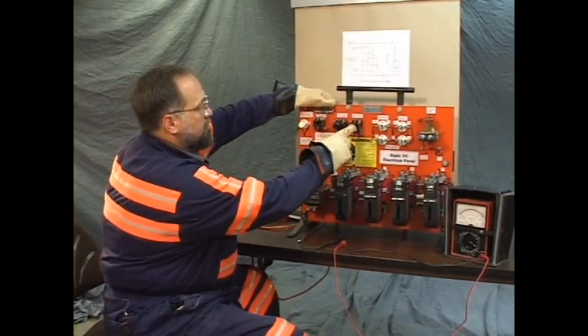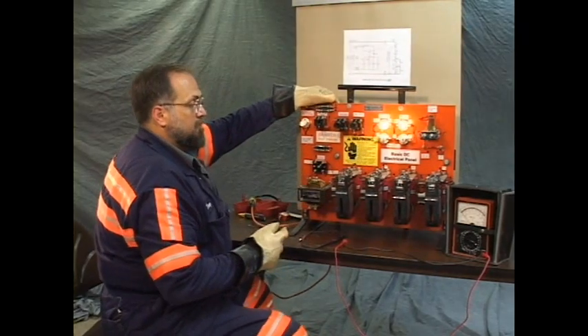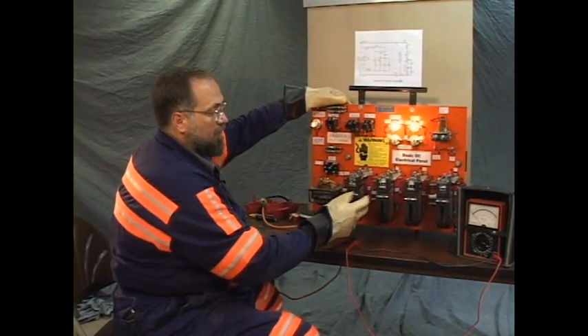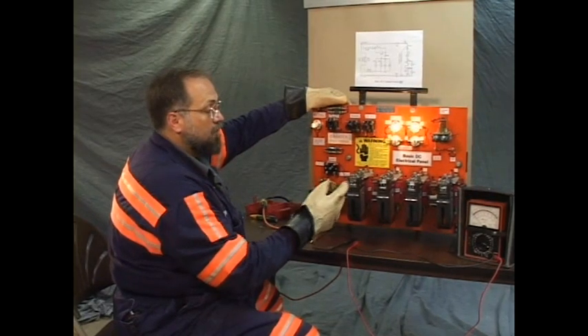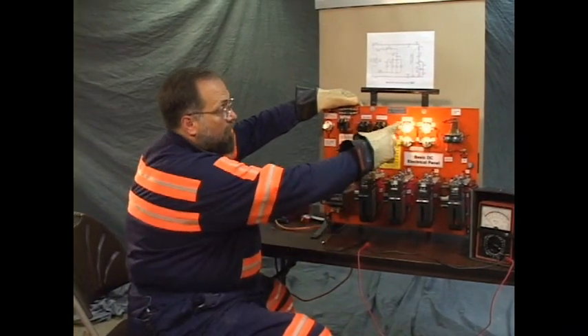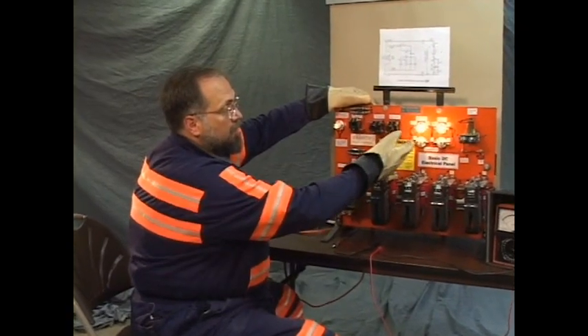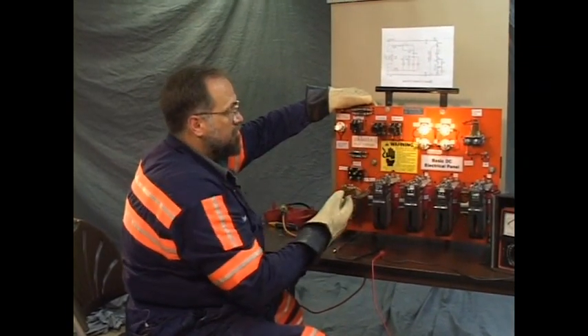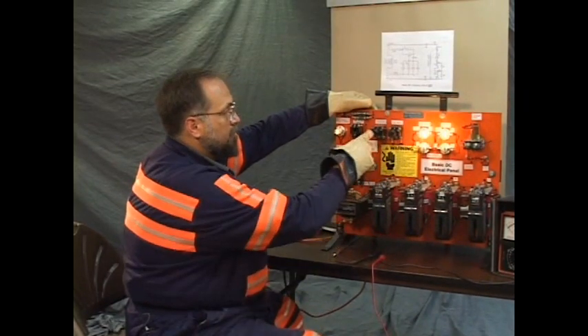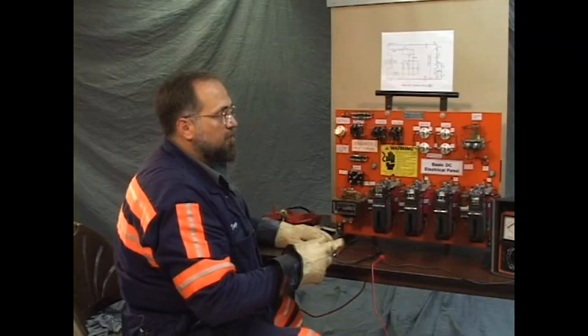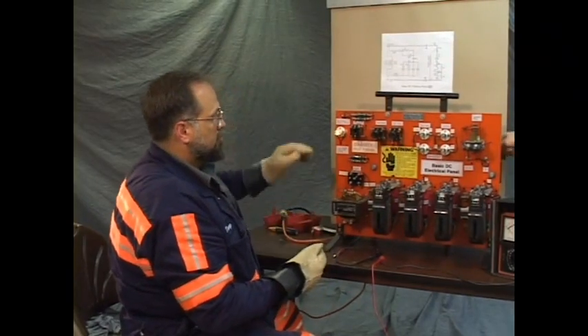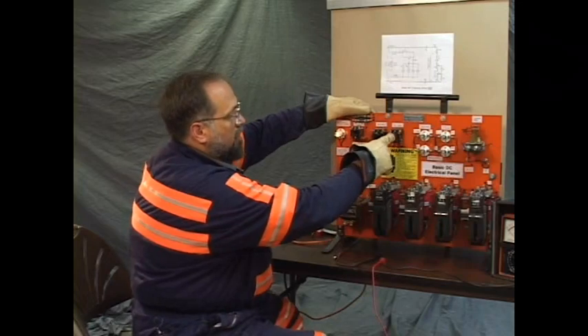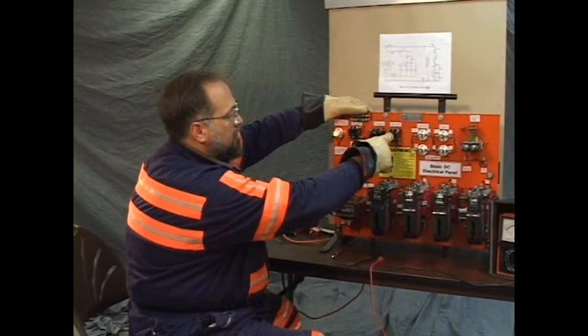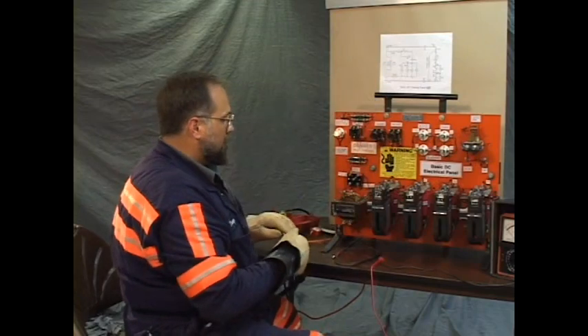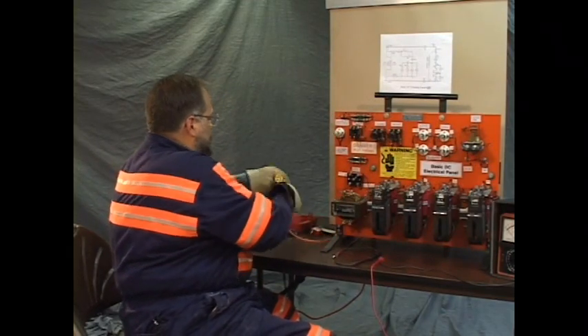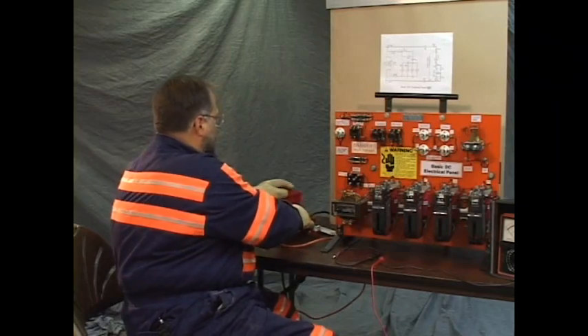When you depress the switch, you noted you had 3 closings. 2 of the contactors closed simultaneously, so they only made 1 click, but 3 clicks. And you had all 4 lights on. When they closed the contactors, some of the lights went off, some of them got brighter. And that's normal operation. But with this problem installed, problem number 2, you press the start switch, nothing happens. Okay. Well, let's take the power off. We're going to lock and tag.